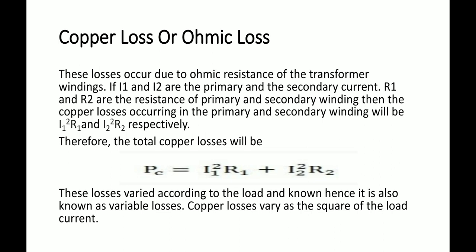These losses vary according to the load, and hence copper losses are also known as variable losses. Copper losses vary as the square of the load current. When the load changes, the current value changes, and consequently the copper losses change. So total copper losses depend on the load.